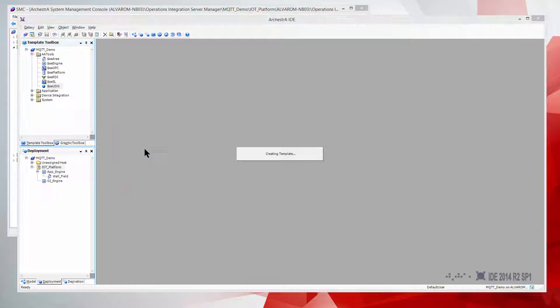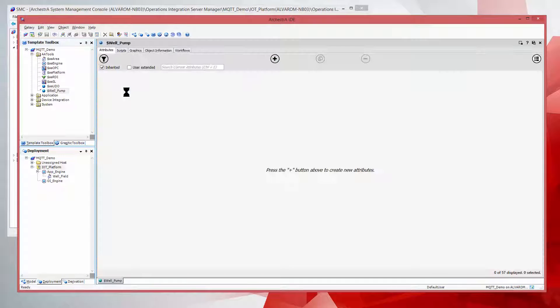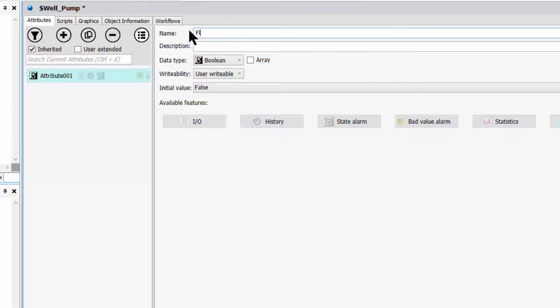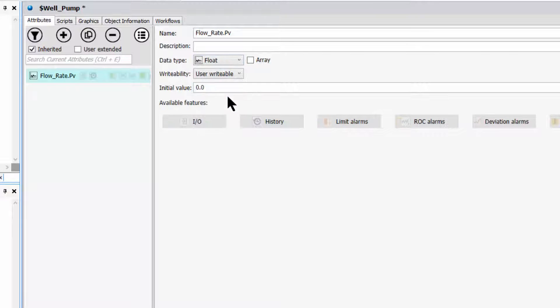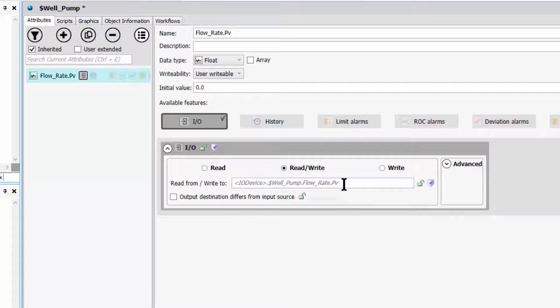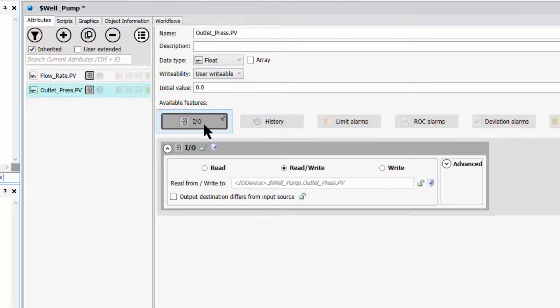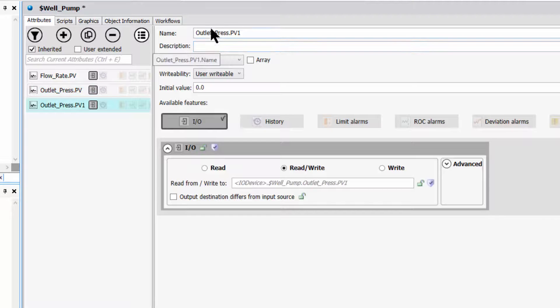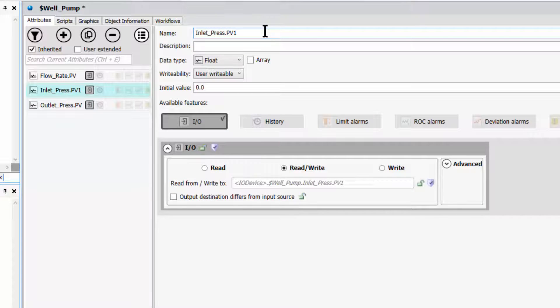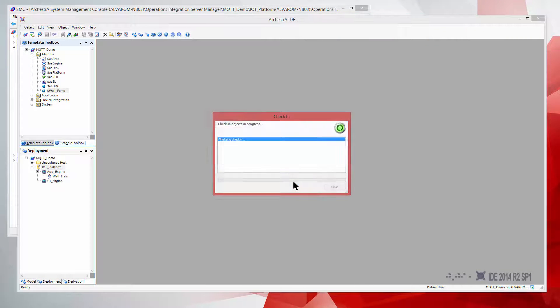First and foremost, I have prepared my derived templates, and now I'm going to create the template specifically for our well-pump connectivity. In this template, I'm creating three datasets. I'm going to be monitoring the flow rate, the inlet pressure, and the outlet pressure. One thing to notice here is that MQTT is case sensitive, so pay close attention when you're using lowercase or uppercase syntax in your connectivity. Very important. I'm also going to be leveraging IO Auto Assignment functionality in App Server, so as you notice, I'm only enabling the IO — I don't need to edit it because I'm going to be leveraging IO Auto Assignment.